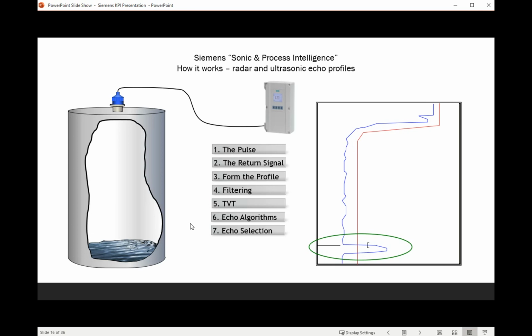Those can be user-defined based on different types of applications beyond the scope of this discussion today. And then finally, it's going to make that echo selection. Depending on the application, it may be performing these 7 steps several times a second, but it goes through these steps each and every time it makes the measurement in order to select what the instrument believes the true echo to be, and it takes a lot of calculation in there to try and filter out the false echoes that you may get from the real world that I live in, which is, you know, a dynamic process.